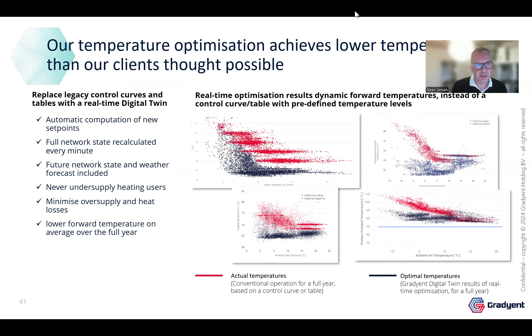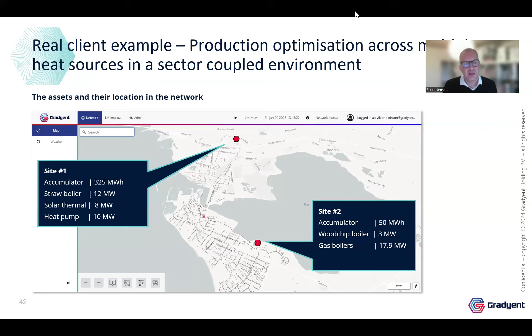Another example where the digital twin provides a lot of value is in production optimization. This is a quite typical example from a Danish client, a small to medium-sized city, with 2 sites. Every site has different technologies, accumulators - one with straw, solar, and a heat pump, another with wood chip and gas boilers, also an accumulator. They're placed at different locations, with the network in between. So how do you operate these assets best and produce the heat as cheap as possible? It almost speaks for itself that it's super complicated if you have to do this by Excel sheets or manual thinking only.